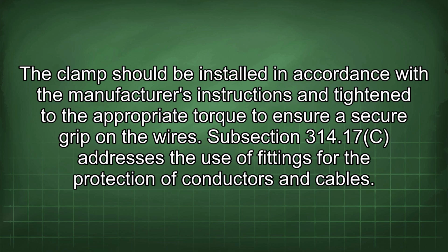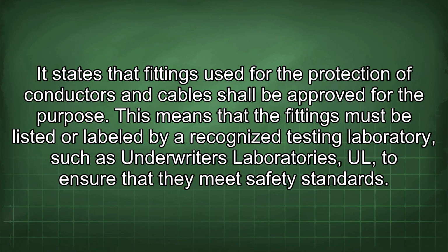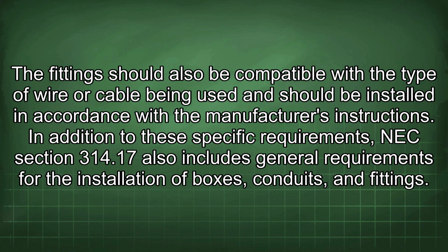Subsection 314.17c addresses the use of fittings for the protection of conductors and cables. It states that fittings used for the protection of conductors and cables shall be approved for the purpose. This means that the fittings must be listed or labeled by a recognized testing laboratory such as Underwriters Laboratories, UL, to ensure that they meet safety standards. The fittings should also be compatible with the type of wire or cable being used and should be installed in accordance with the manufacturer's instructions.